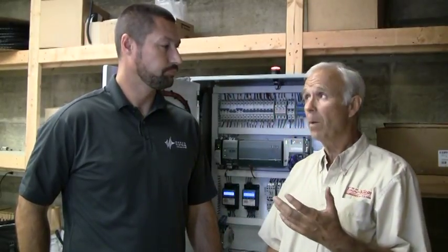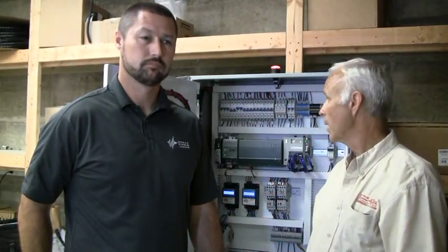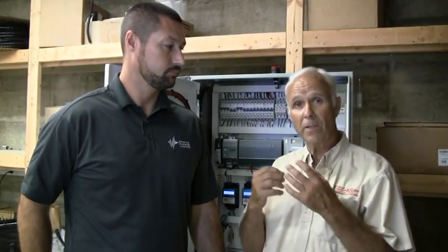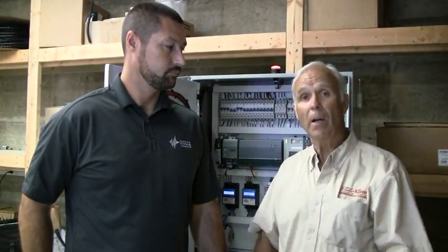So in closing, I'd like to inform the Public Works Director and developers that we're a green station, we're a green company. We believe we're the first all-green pump station. And to that point, talking about pumps and the controls, if you don't have good panels, if you don't have good NEMA 4X seals, if you don't have good controls sending good clean signals to your pumps and motors and switches, then you're going to have problems. And part of problems are either outages or premature failures. I think the industry knows that green is making something last longer. You don't want to be recycling your pump station. You want to keep it there for years of dependable performance.